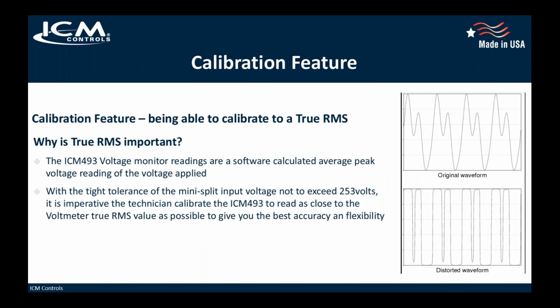Okay, so our calibration on this. Now, because the 493 is not a true RMS meter reader, it reads the voltage as a peak voltage rather than a true RMS reading. Your voltmeters, your Fluke voltmeters, for example, will read true RMS values because they're a very expensive piece of equipment that is made just for that purpose.